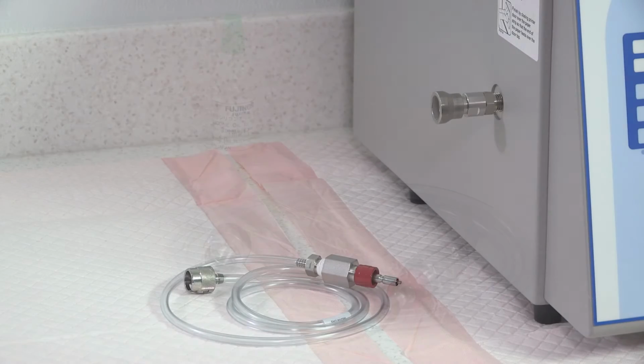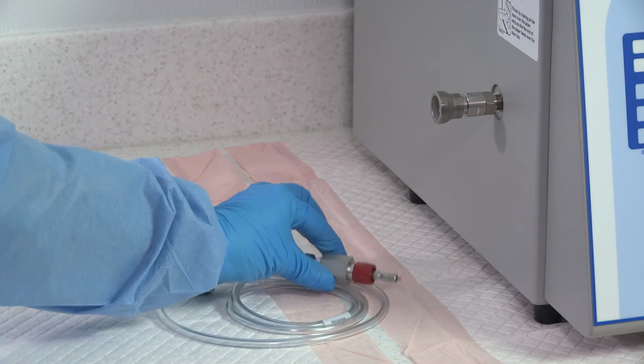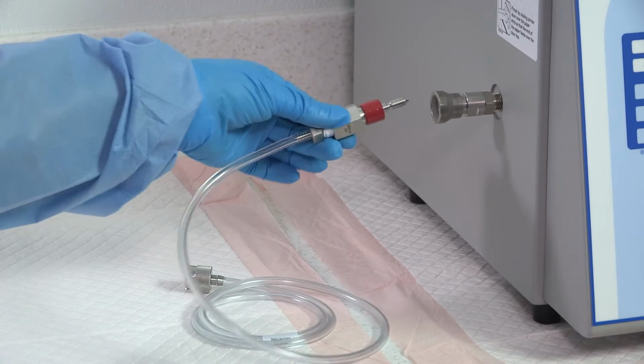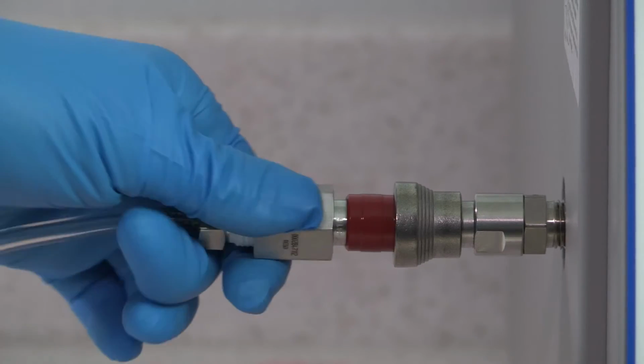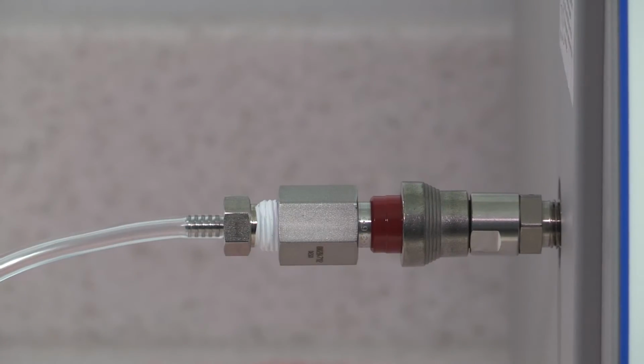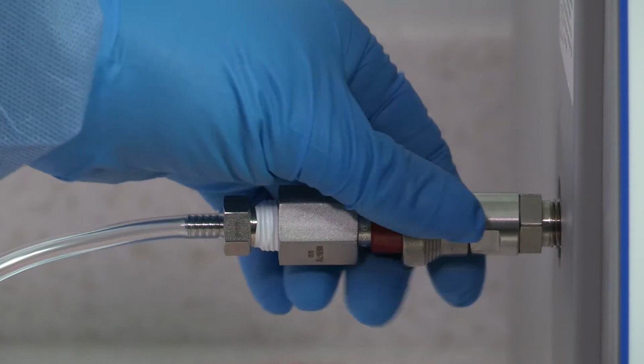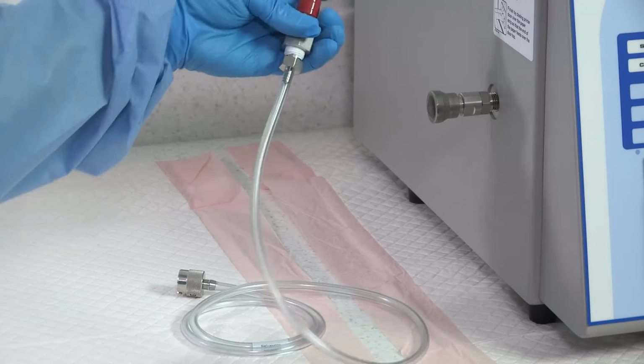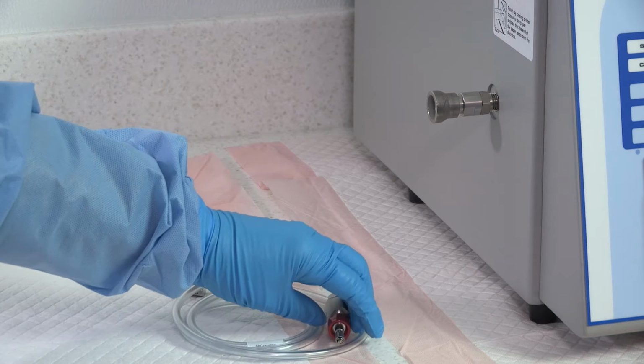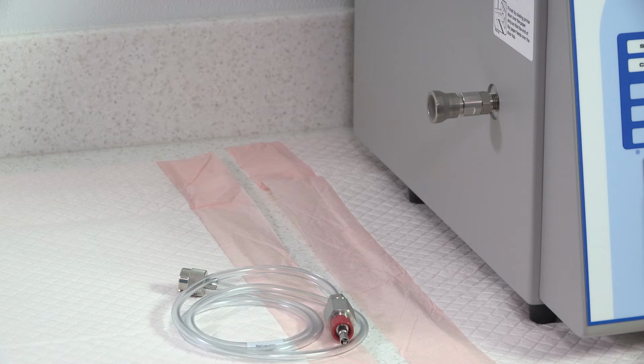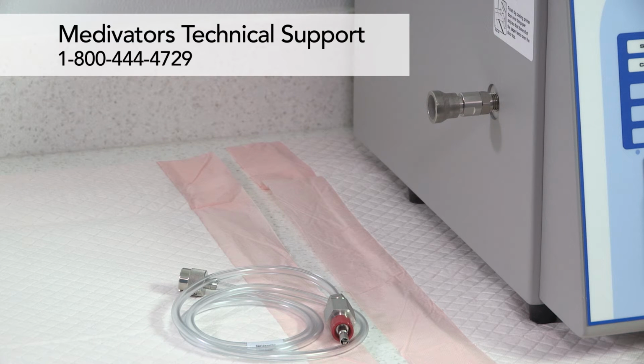Insert the quick connect tubing metal prong into the quick connect port located on the side of the unit and apply inward pressure until it clicks into place. To remove the tubing, pull outward on the quick connect port's outer metal housing until the quick connect tubing is released. Always have an extra quick connect tubing. If a replacement or additional quick connect tubing is needed, contact Medivator's technical support at 1-800-444-4729.